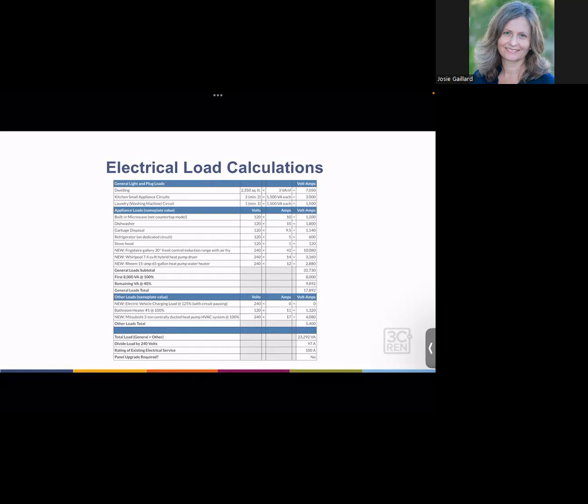That's in contrast to an EV charger that is not a motor. It comes on at a certain level and stays at that very high level for a very long period of time, which I suspect has a risk of overheating wires, which is why the code requires you to apply that 1.25 coincidence factor. Does that answer the question? Tom, feel free to jump in with any additional comments there.